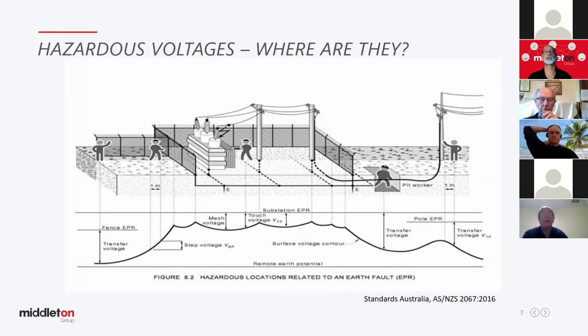I did show this one in the last presentation, but basically it shows the zone substation. We could have people working in the sub, the public outside, even at a fence many metres away from the sub. We can have people working on cables. We can even have this guy who jogged up and he's having a bit of a rest against the pole there. And if this pole is a conductive pole, it's likely bonded back to the zone substation too.